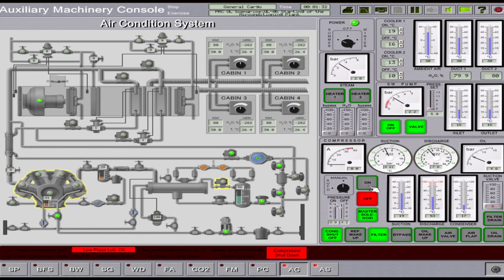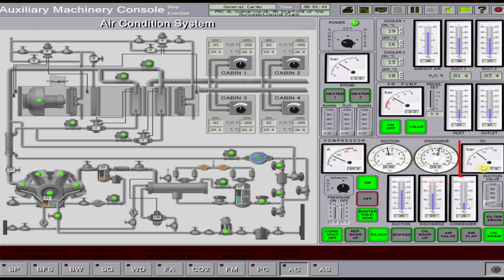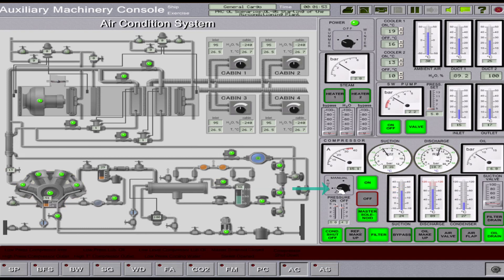Then, run the compressor. After running the compressor, open the suction valve to at least 5 to 10%. Then, check the lube oil pressure if it is running normal. Set the operating mode switch of the compressor to auto running position.